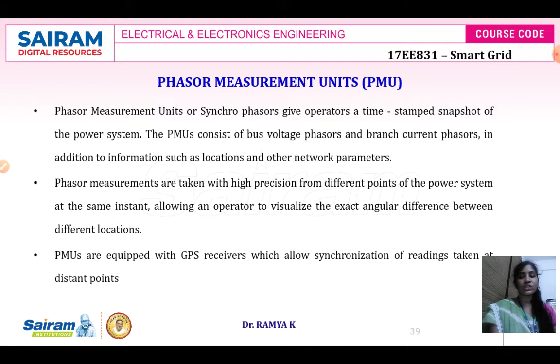In addition, with respect to location and other network parameters, the information will be provided by the phasor measurement unit. Phasor measurements are taken with high precision from different points of the power system, and at the same time the exact angular difference will be available when we take real-time measurements at different locations. Next, it will be equipped with a GPS, that is, Global Positioning System receiver, which allows the synchronization of the readings taken at different distant points.